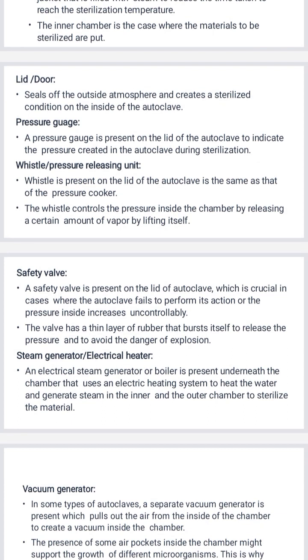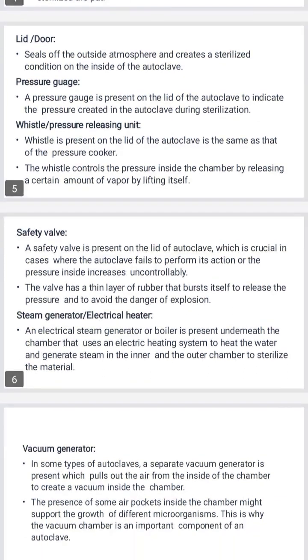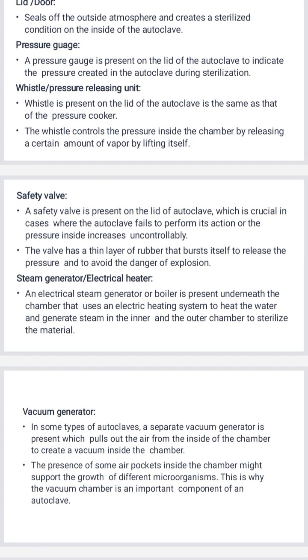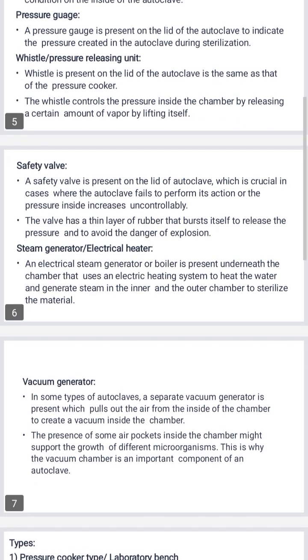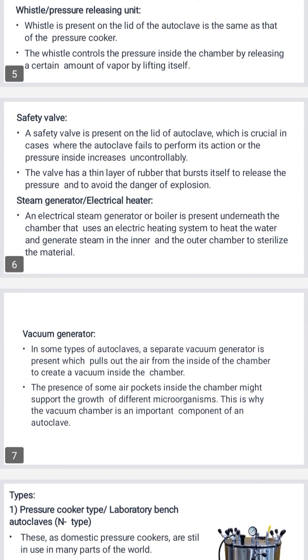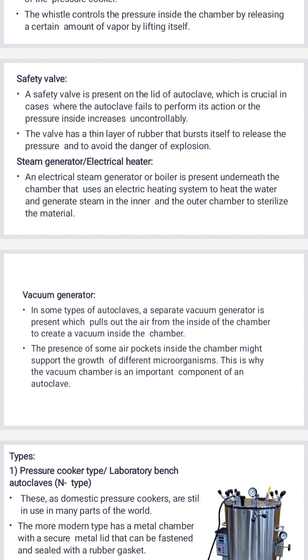The steam generator or electrical heater is also a component. An electrical steam generator or boiler is present underneath the chamber that uses an electric heating system to heat the water and generate steam in the inner and the outer chamber to sterilize the material. The vacuum generator also comes in the components. In some types of autoclave, a separate vacuum generator is present which pulls out the air from the inside of the chamber to create a vacuum inside the chamber.